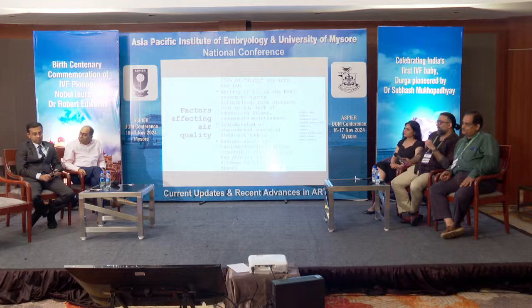There are a lot of things, and please understand that human beings are the major source of contaminants. The more people enter the lab, the more people walk in, the more the contamination increases. There is a study which shows that a human being who just sits in the lab generates so many particles. If the same person gets up and walks, it generates more particles. If the person does some frenzied activity, the particle number gets multiplied. So we are the major source of contaminants, and it is important that we restrict ourselves in the lab.